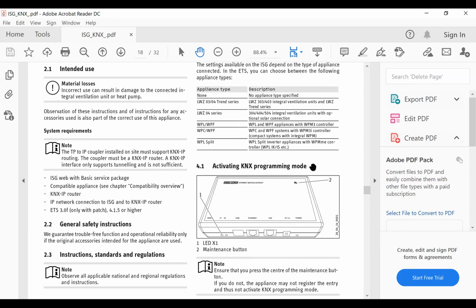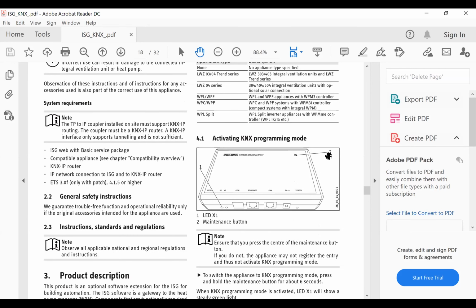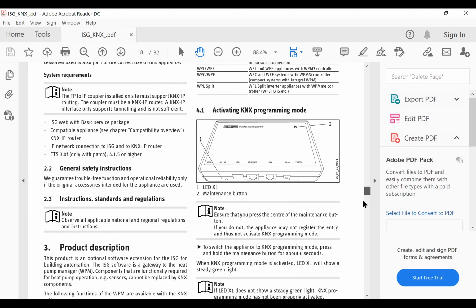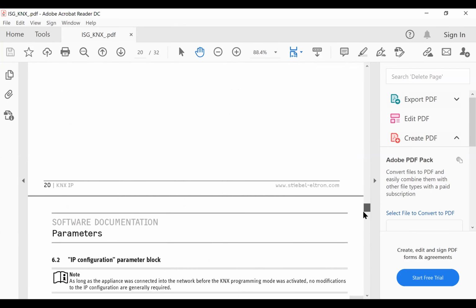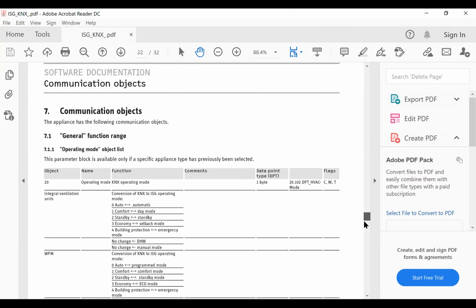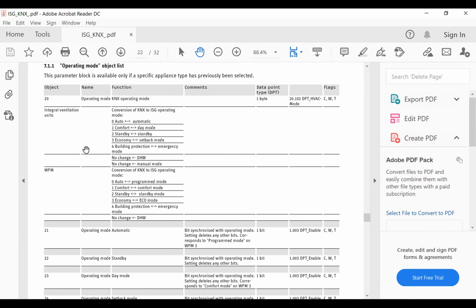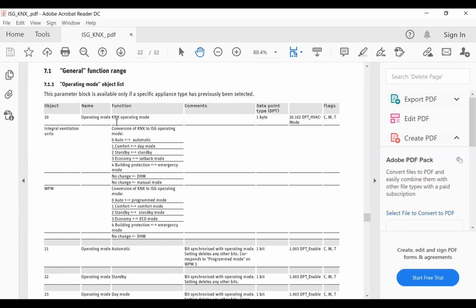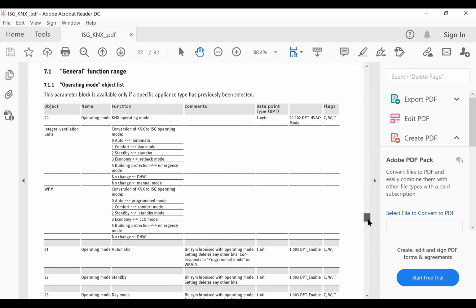But if there is, within reason from the WPM, just with the functions I've showed you, if there is a requirement for BMS integration, then an ISG gets installed, which should be there anyway, and the KNX controller will actually go in and find our ISG through the network. It's a network control thing. Okay, I'm not going to go through everything here, but this just gives people a bit of an idea. So this gives 2-way data transfer all of a sudden. So someone could have a very fancy BMS system operating their whole house, their garage door, everything. And they're able to not only send cues to our heat pump system, but they can get them back from the management system, saying what mode I'm in, what buffer temperature I am.